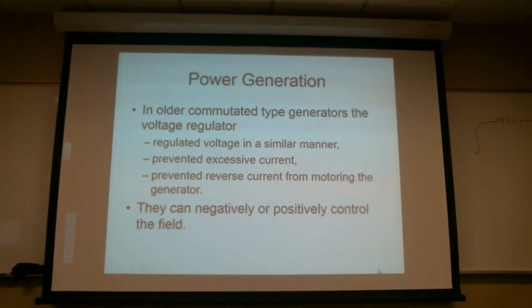What they do is actually kind of stupid, a little suicidal I guess is the way to think of it. They do what's called a crowbar safety device - it's like taking a crowbar and hitting yourself in the head with it. I don't know why they use the term crowbar, but essentially part of the voltage regulator circuit says if the voltage goes too high, I'm going to take the input lead coming from the circuit breaker and attach it to ground. That's going to dead short the circuit breaker, causing it to pop, which shuts everything down because the voltage went too high.